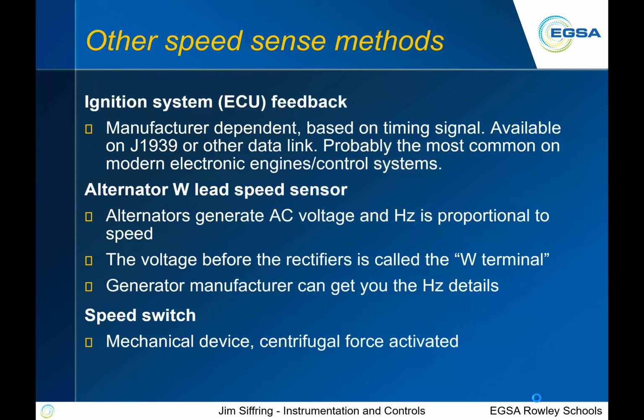Other places to pick up speed sense, if you're looking to have something give you speed feedback: ignition systems, J1939 will typically give you some sort of a speed output. Alternator, you can pick up some leads off the alternator, off the voltage regulator, and get some signals out of there. And sometimes you just want something as simple as a mechanical speed switch with flyweights. Don't see those a whole lot anymore, but you might see them in older devices, older engines.